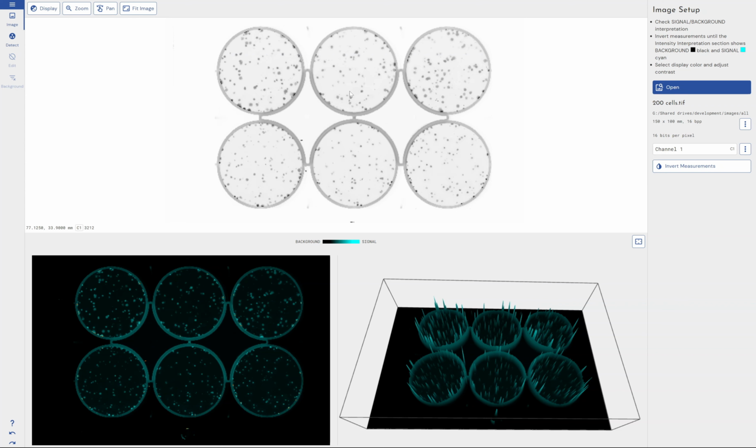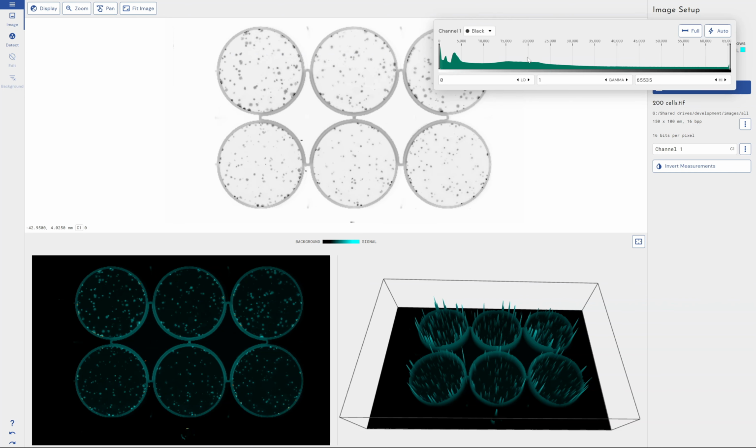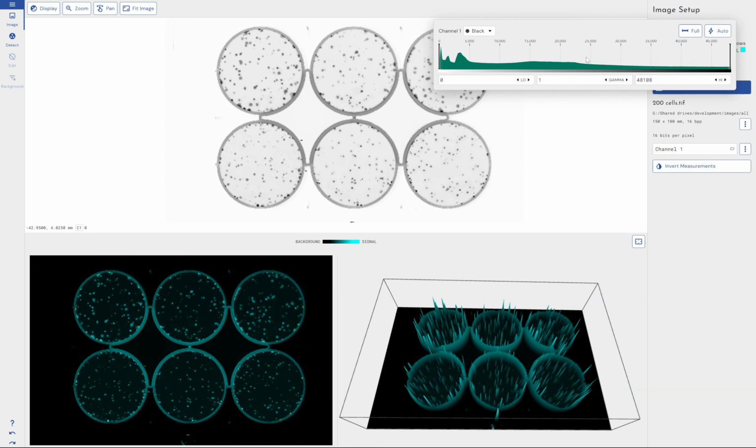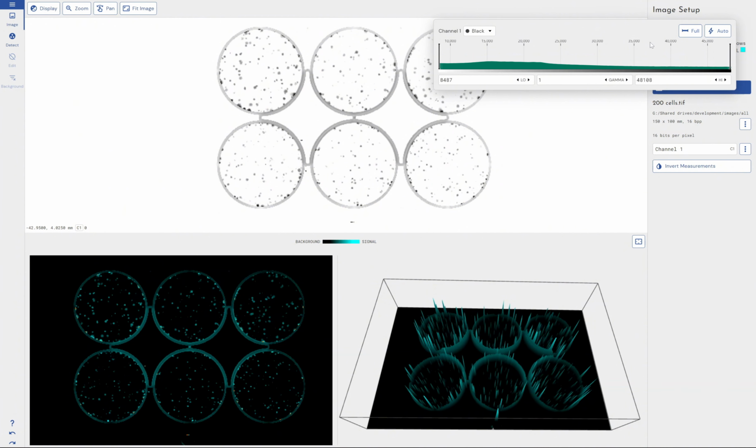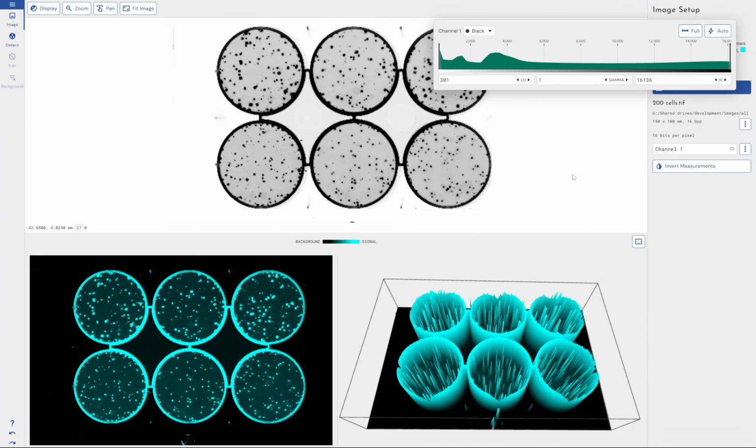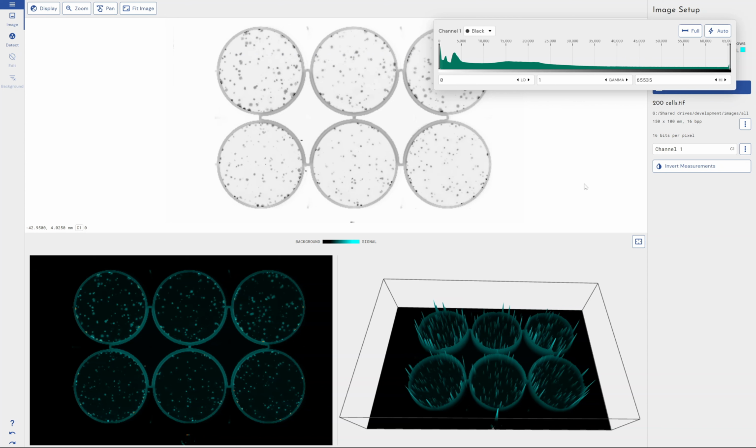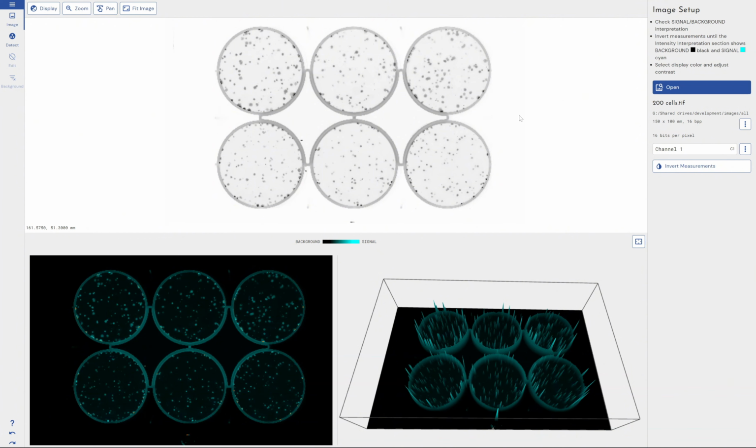So we see here, and if you've seen any of the other Phoretix image analysis software videos, you'll know what the setup is. From here is where we control contrast and the display, and you can see how as I change these bits, the visibility of the image changes. It's worth noting that no matter what settings you apply here, the visualization doesn't change the results. So we're always taking the results from the raw, ideally TIFF image. This is purely a visual aid for the operator to be able to define areas of interest, define specific spots and things like that. So it's visibility for you.